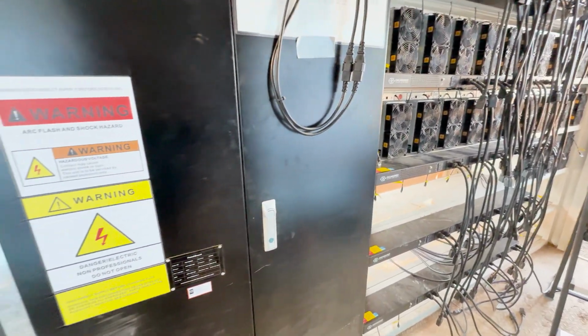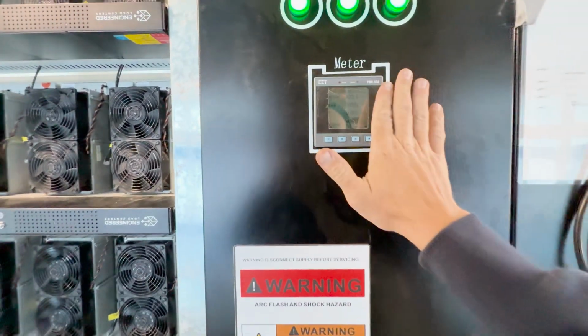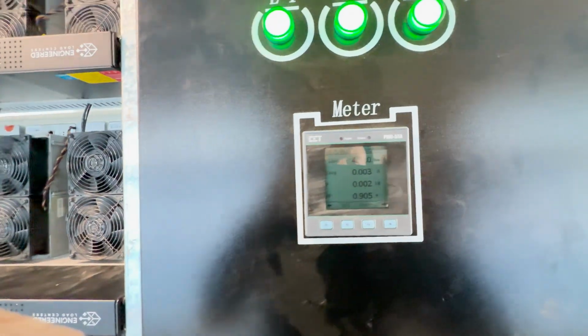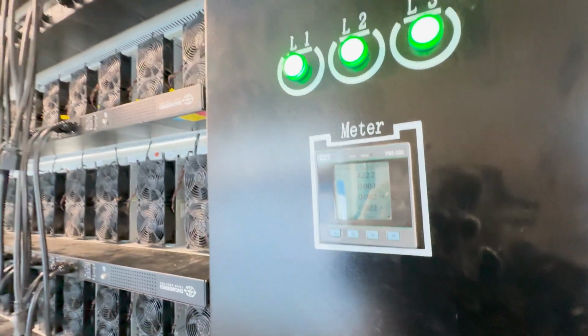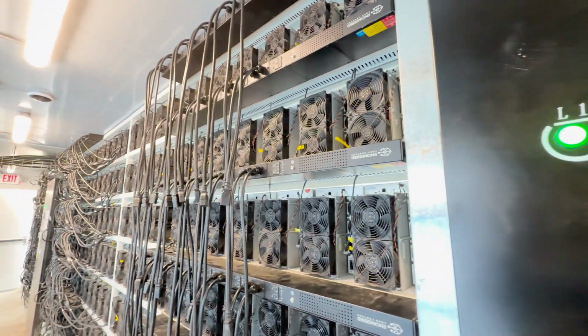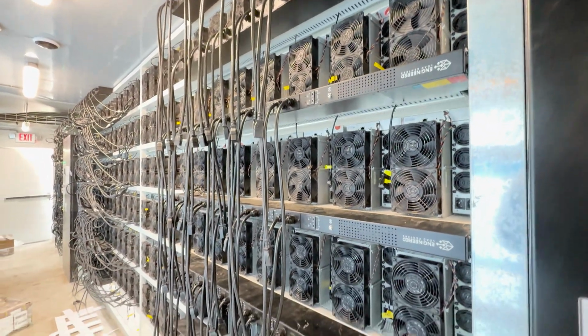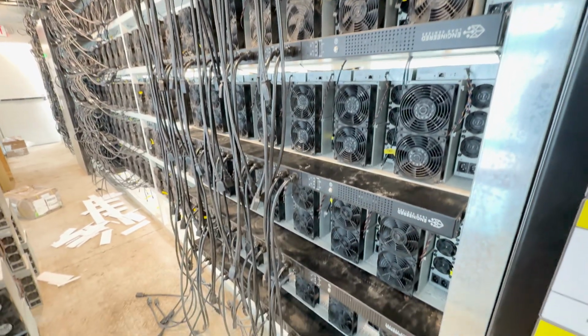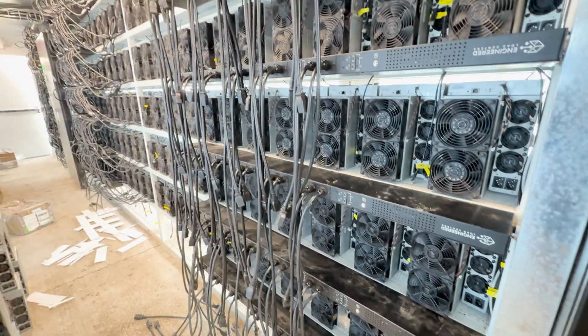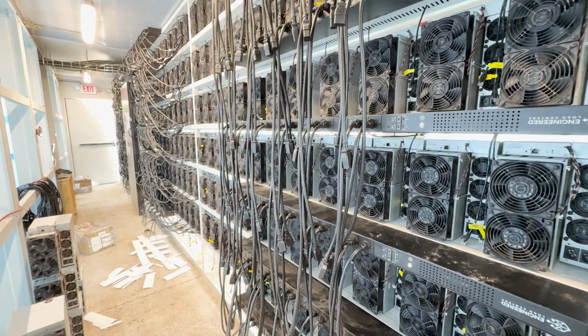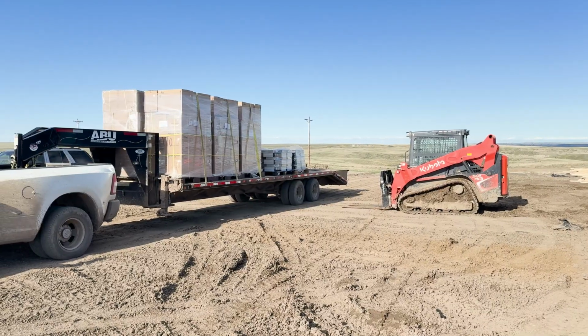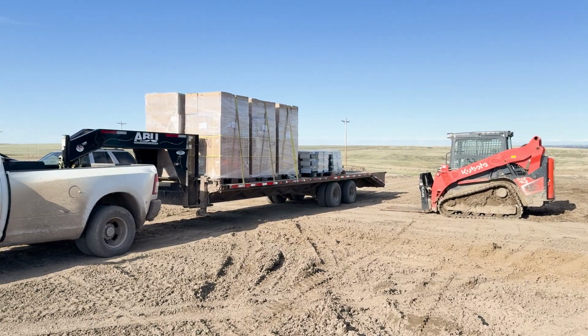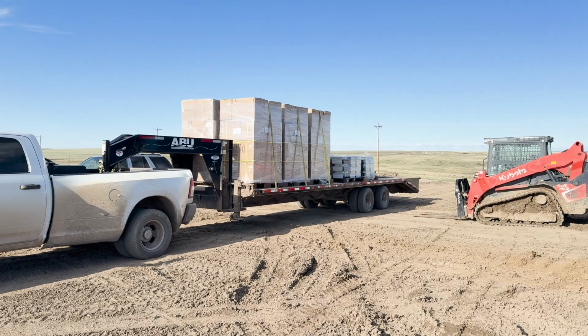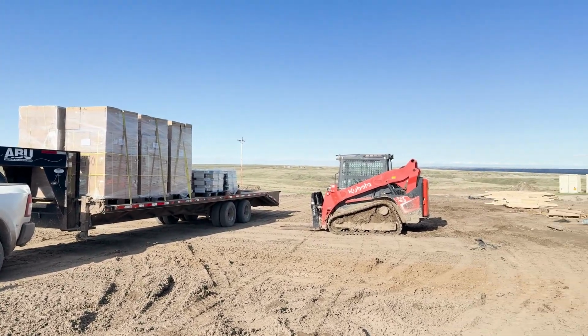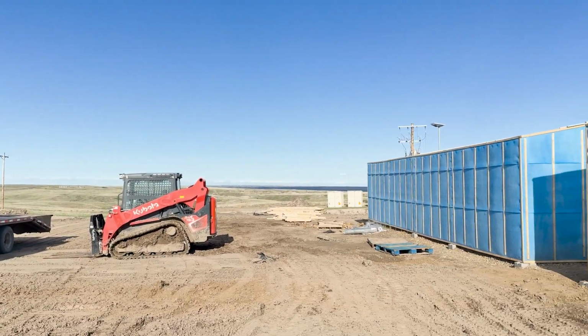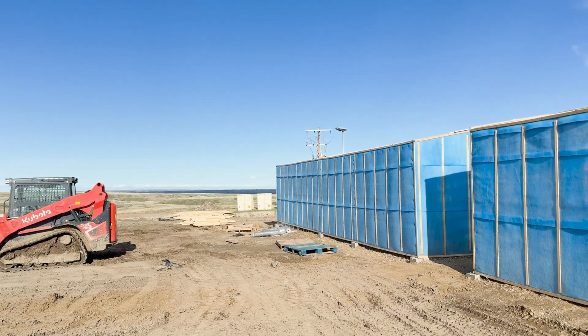And then also the other main hurdle we had was the PDUs. The PDUs have to be fused, and they have to have a high AIC rating for North Dakota. So we had to swap out our PDU. That's one of the reasons why we only have three containers that are good to go in terms of occupancy permit and electrical inspection, so we are going to be mining on those. As we get more PDUs coming in, about three to four weeks, once we swap those out for the other two containers, we can power those ones on as well. So it's a step-by-step process, but we are good for three containers.